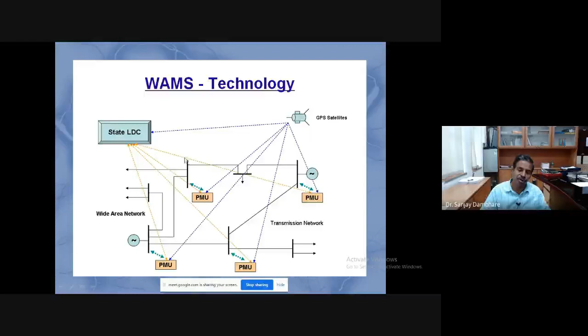The preferred communication is fiber optic communication because the latency is very low, and the time signal is common, the time tag is common. At this point, the PDC, the phasor data concentrator, aligns the data having the same time signal received from the PMUs, and that is how it is then further processed. So this gives quite good information on the fiber optics based conventional current differential relay.